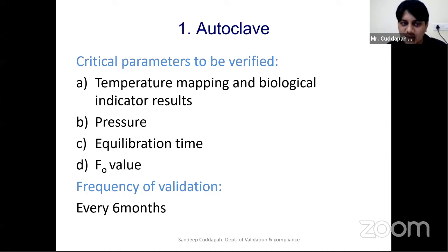As an example, if you take an autoclave, any equipment you take in your laboratory, you first list out what the equipment is used for. Then, to do that actual usage process, what sub-components are connected to it, and what are the parameters or key controllers for this process that you have to list. So for an autoclave, what is required? You have to achieve temperature, you have to achieve a certain pressure, and as per guidelines, you have to achieve equilibration time, and F0 value is your lethality rate. These are the key core parameters.